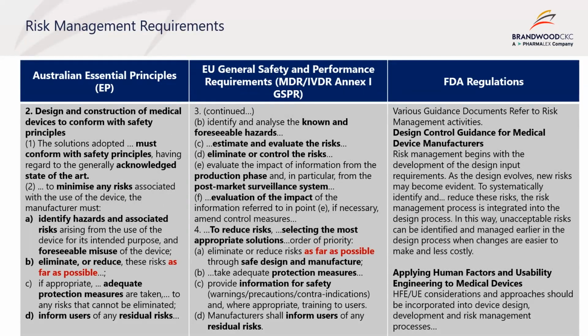Continuing, both the Australian and EU regulations also include requirements for identifying hazards and associated risks, evaluating those risks, and eliminating or reducing the risks as far as possible during the design, production, and post-market phases. They also include acknowledging the state of the art when considering solutions for conforming to the safety principles, such as identifying existing potential hazards with similar devices. The options for reducing risks include introducing safe design and manufacture, adding adequate protection measures, or informing the user of any residual risks.